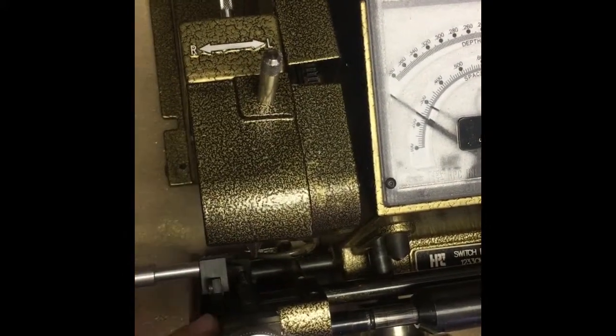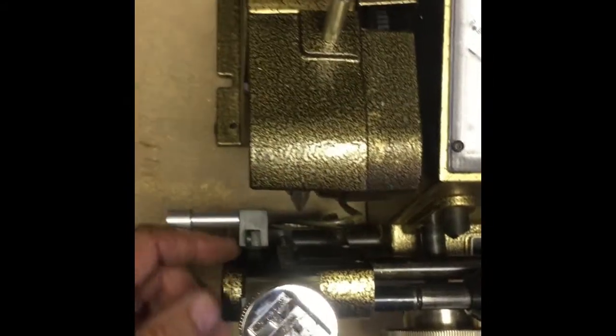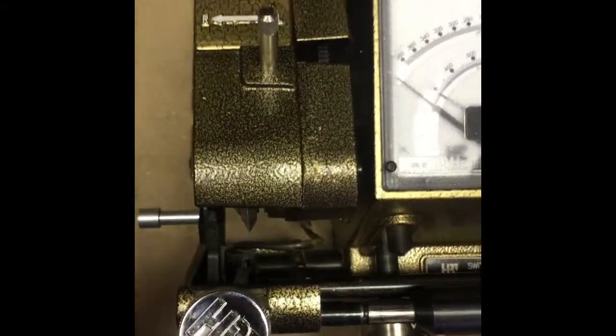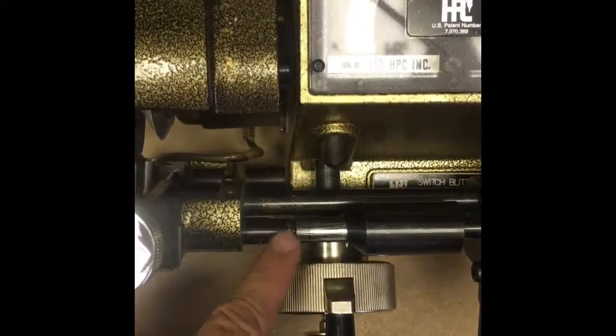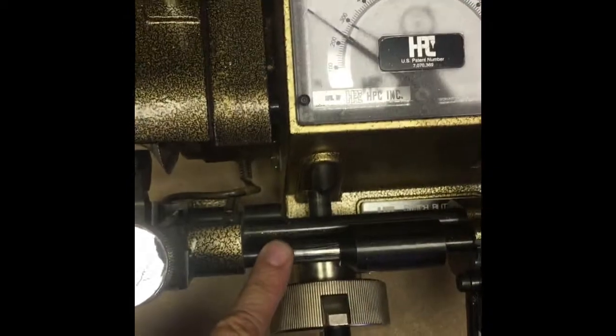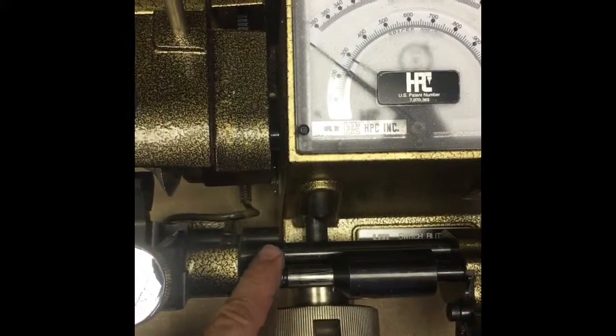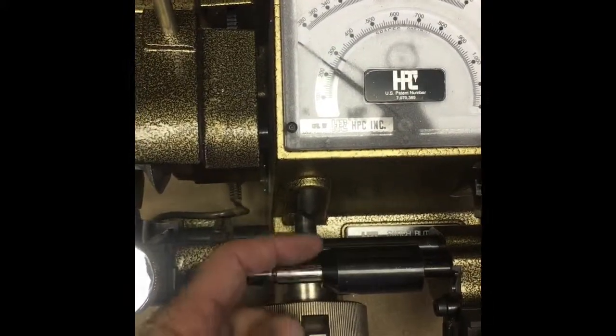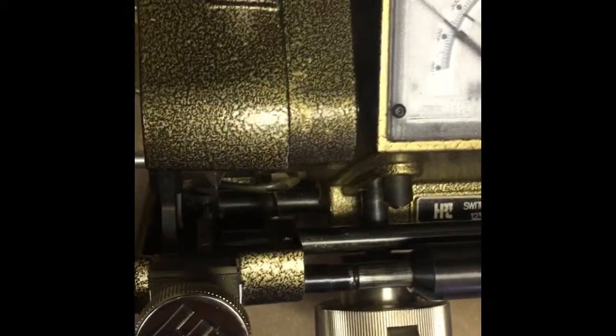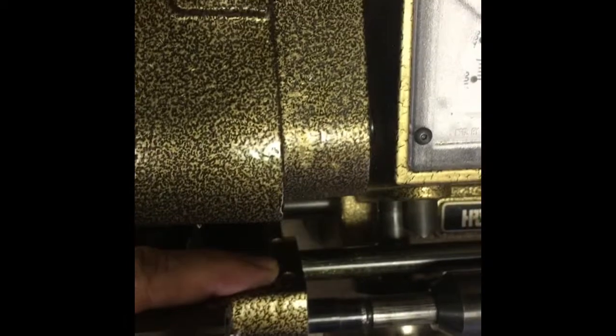In order to move this right and left, unlike the switch Blitz, there's actually a little screw point on the side over here that you can turn and it'll move right to left. So that's your spacing. That shouldn't be very difficult. And then when it comes to your depth, you're going to be adjusting this rod here. Now this is not round as it appears. It has a little bit of an oval shape to it. So as you turn this, it'll actually move this further or closer away very minutely, but it's enough to make a difference when calibrating. And for that, you have a screw right here that's also an Allen wrench that you would loosen up in order to make that happen.